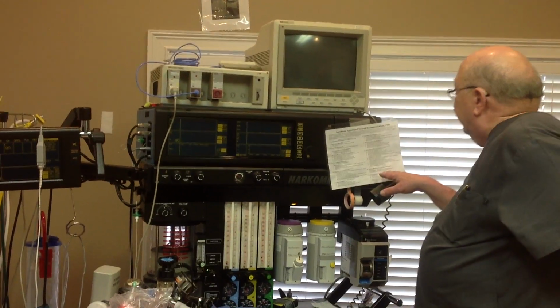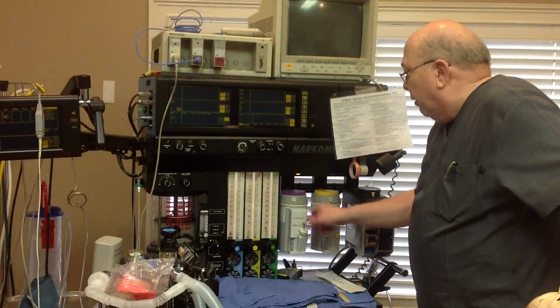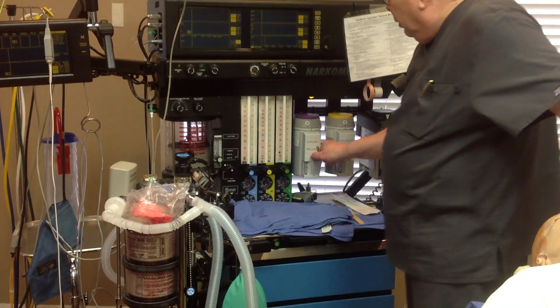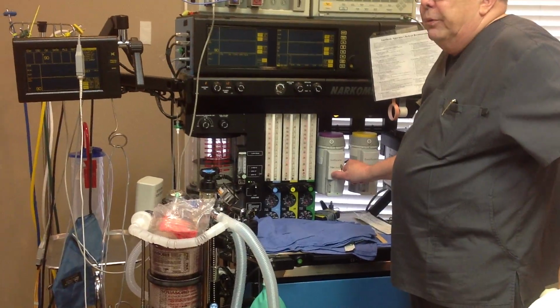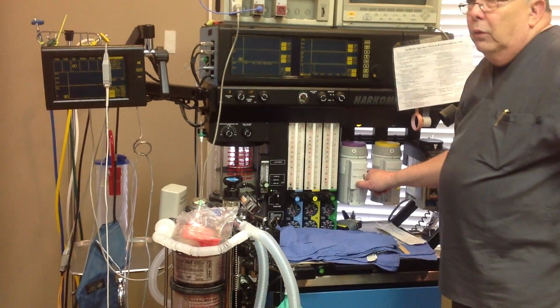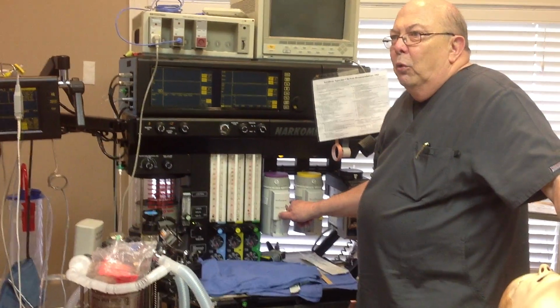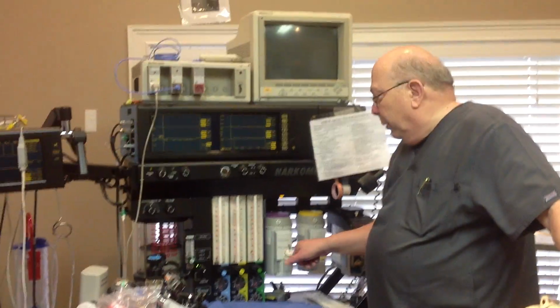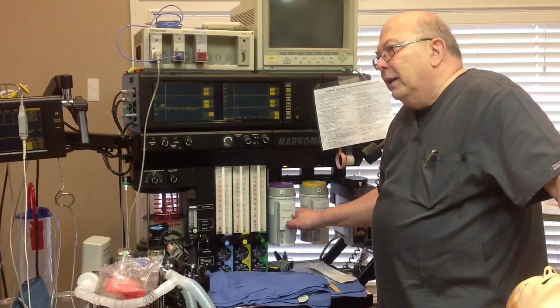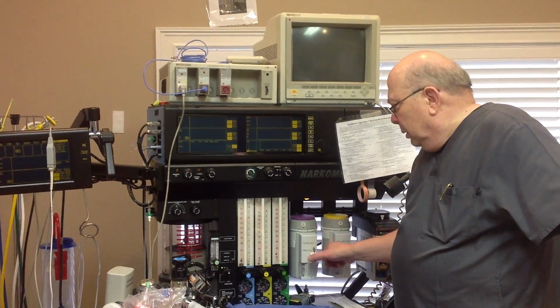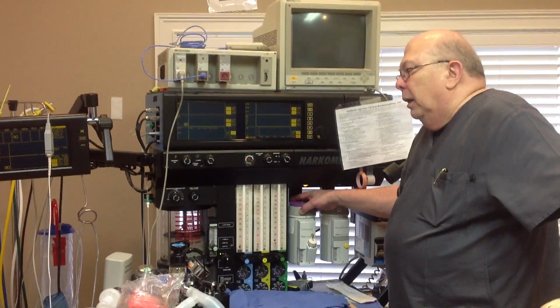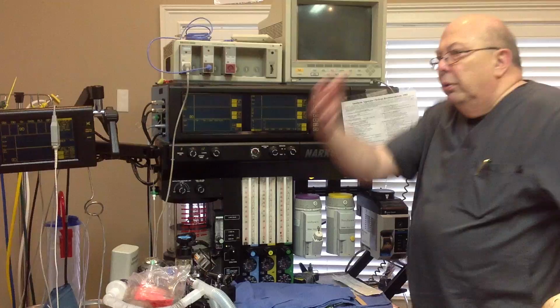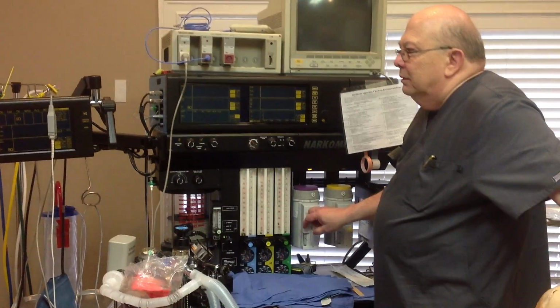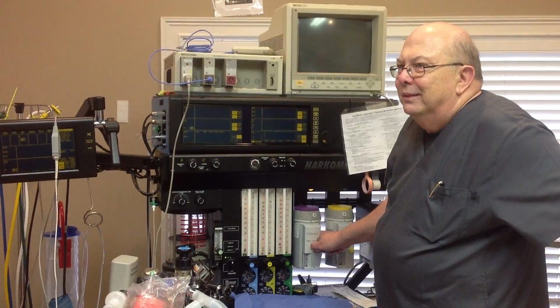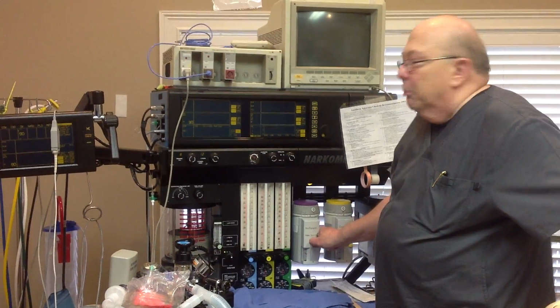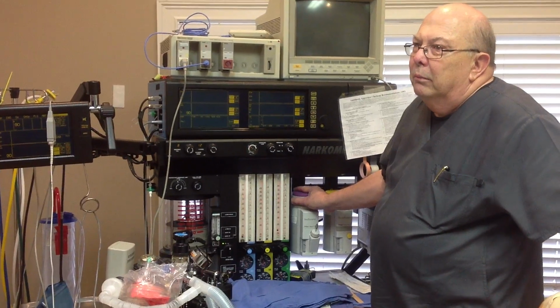And so the last step is just to make sure the vaporizers are off, make sure your caps are on, and when you're checking your vaporizers, always make sure these filling caps here are good and tight. That's another area: when you come in the morning, or if you come back in between your cases, somebody may have filled your vaporizer for you, and they didn't tighten it all down. So if it was open, as soon as you have oxygen flowing and as soon as you turn it on, it's going to spray isoflurane all over the place. Oh. Okay. It will happen. It just happens to everybody. You have to be vigilant and make sure you do these things every time.